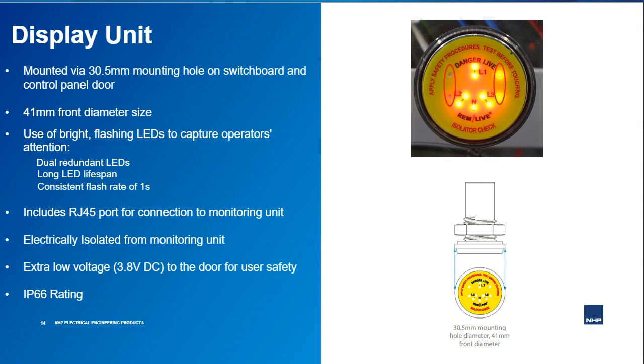Similar to the monitoring unit, the display unit also includes a RJ45 port, which is located right at the back of the unit. It's used to connect the RJ45 cable and establish that connection to the monitoring base unit. It's worth mentioning that this display unit is electrically isolated from the base monitoring unit, which monitors voltages from 24 to 1000 volts, and so the user is protected from such dangerous voltage levels interfacing with the display.